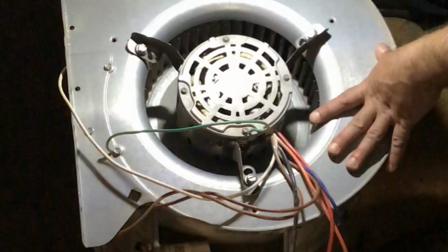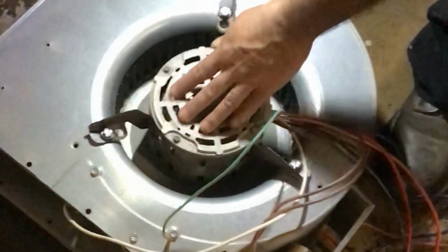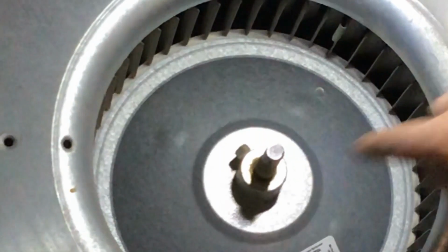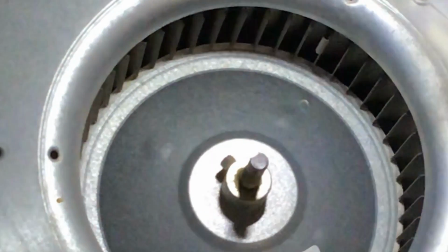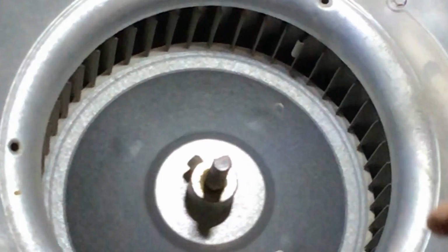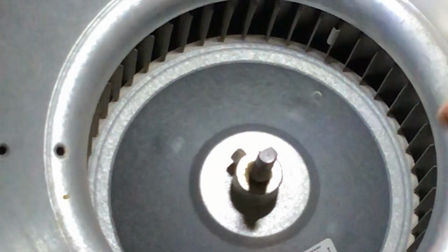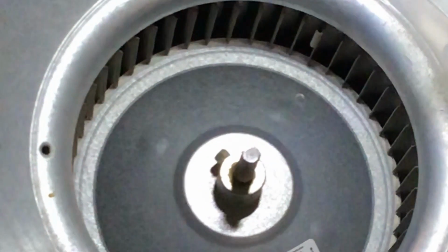They don't come like this. You don't replace the entire cage and fan assembly. You only replace the motor. Three bolts. You're going to flip it around. You're going to have a set pin. And they make a puller device that makes this easier, but typically if you lubricate this up well enough and have it unbolted from the other side, the weight of the motor will let it fall out very easily.